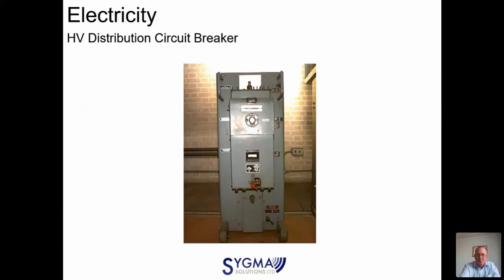You don't need to know about a circuit breaker truck. If there was such a thing in this country, that is an average 11 kV distribution substation. Whilst we say don't take this as gospel, generally when you look at a substation from the front on, your HV would usually be on the right, and the LV would usually be on the left. So that would give you a clue. If your plans confirm that as well, then great. That may be your only option for tracing out the HV. Once you've done the LV, induction on the right-hand side of the sub might be your only option.